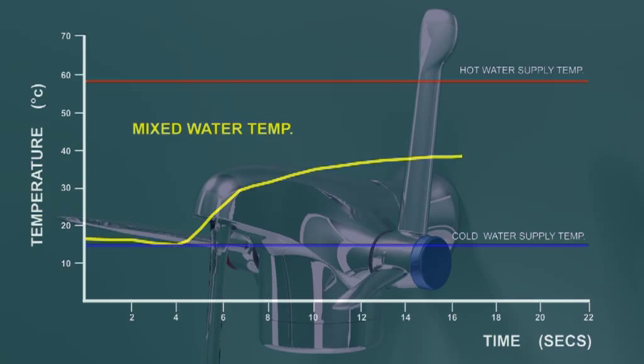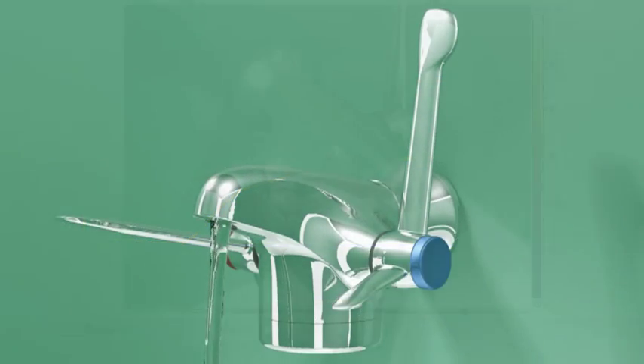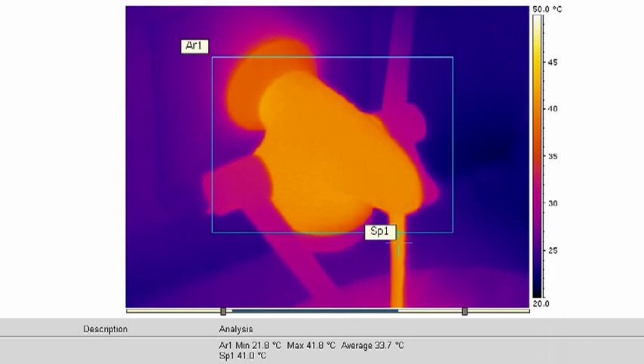The health guidance note, safe hot water and surface temperatures, recommends that no surface within 2 metres of floor level should exceed 42 degrees centigrade. This thermal image shows the OptiTherm thermostatic tap in use. The parameters at the time were hot supply temperature, 60 degrees centigrade, cold supply temperature, 17 degrees centigrade, mixed water temperature, 41 degrees centigrade.